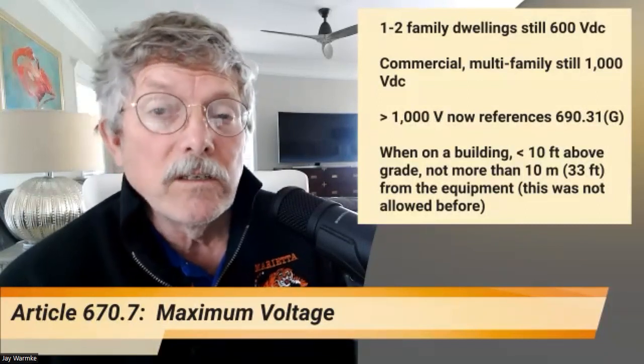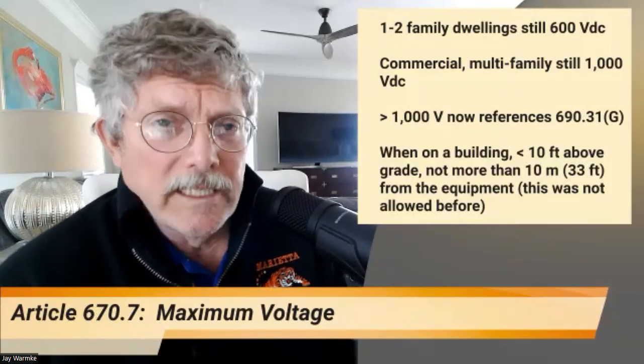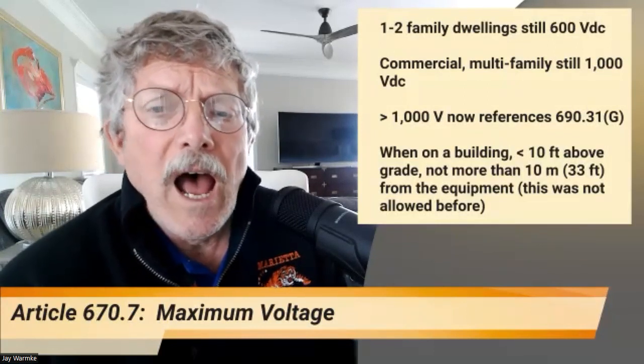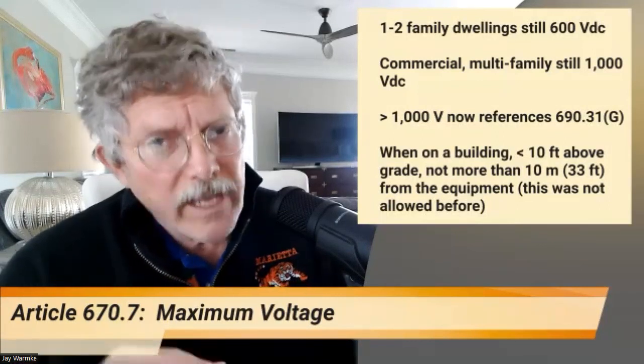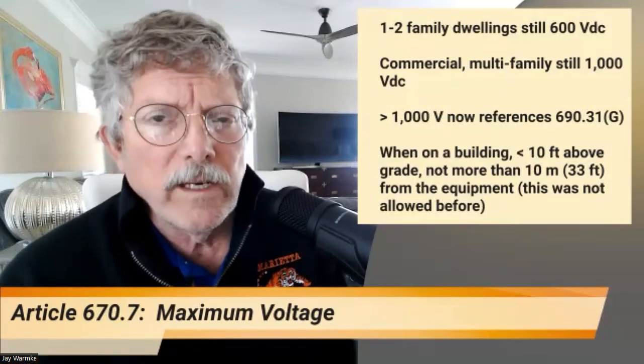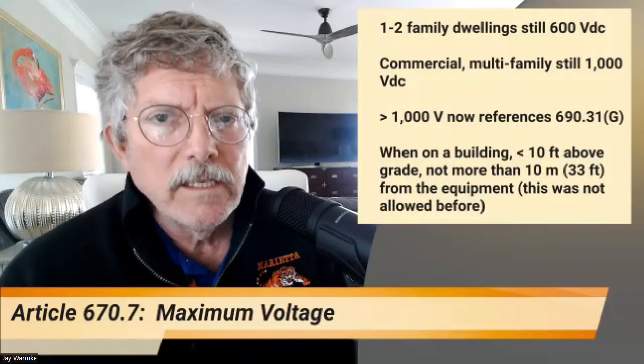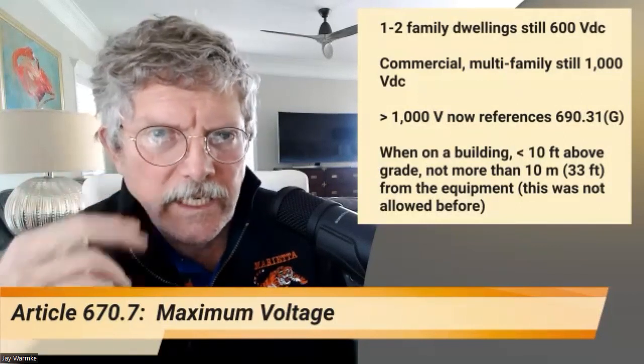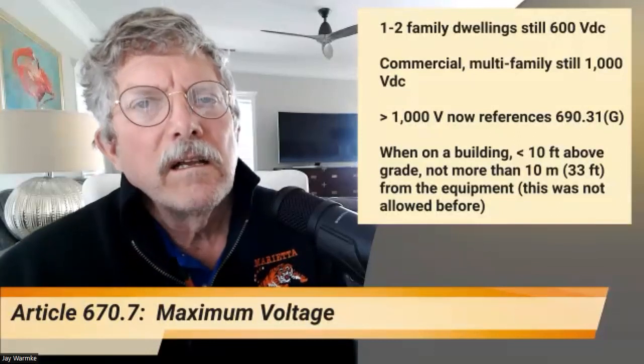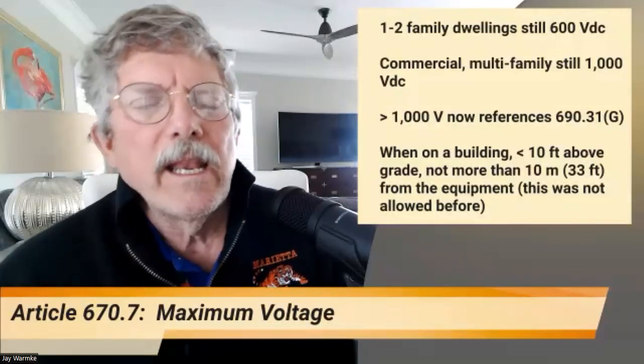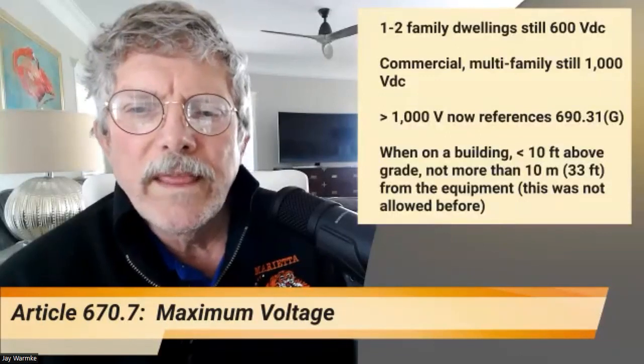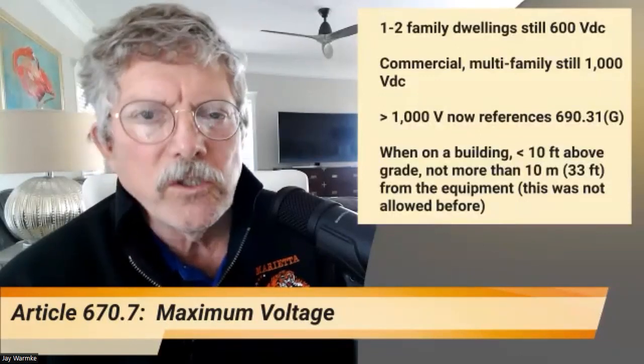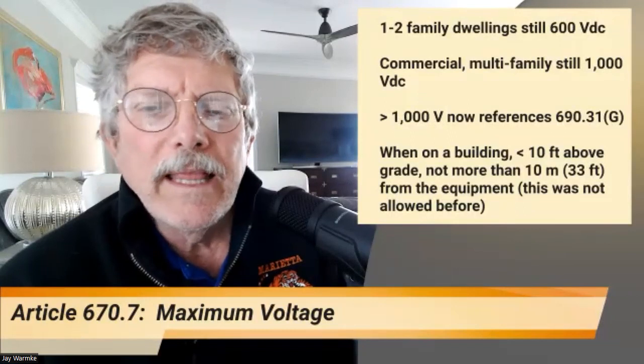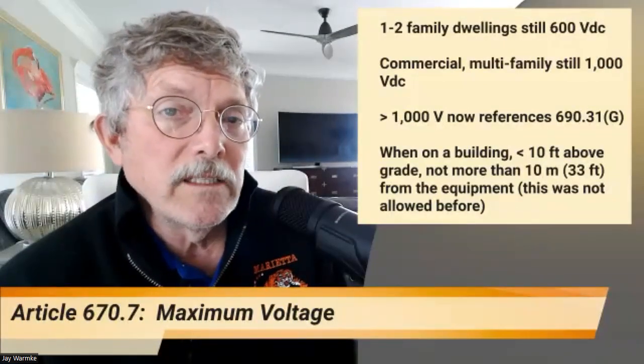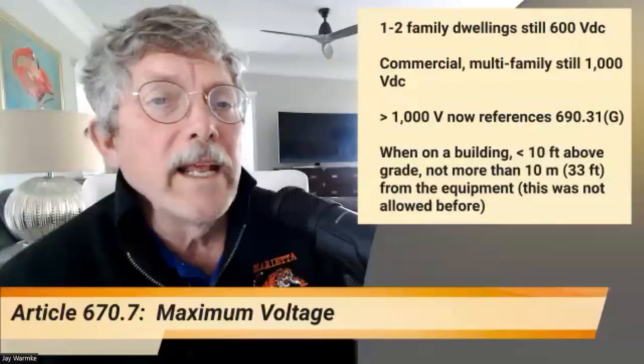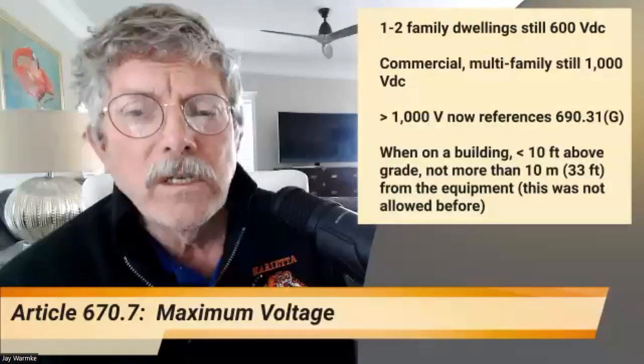So there's some significant cost savings that can be found by increasing the voltage. But the National Electrical Code has been hesitant to increase this. I'm wondering, what they've done is they said, okay, with this round, we're still going to limit residential 1 and 2 family dwellings to 600 volts DC. We're also going to still limit anything that is on a building to 1,000 volts DC, so that's commercial and multifamily. And then they set up a new article for anything greater than 1,000 volts.